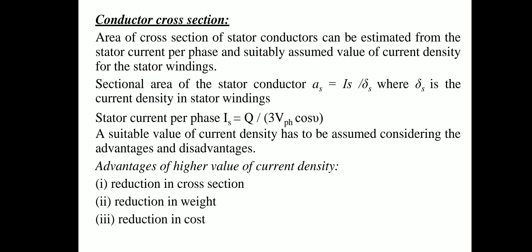The cross-sectional area of stator conductors can be estimated from the stator current per phase and a suitably assumed value of current density for the stator windings. Sectional area of the stator conductor: As = Is / δs, where δs is the current density in stator windings.